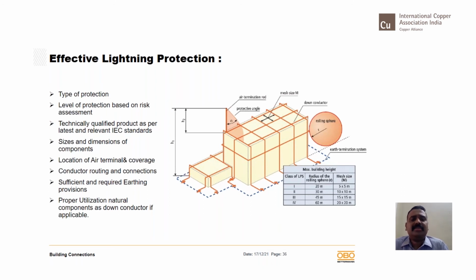Then the location of the air terminal and its coverage. This is very critical, because if you locate a terminal and say a coverage area of this much is being covered in the building, you have completely done the design. Finally, when it goes to the architectural purview, they may say, if you have the terminal here, the aesthetic of the building is getting spoiled, so please relocate it elsewhere. If you do that, obviously that particular area getting protected will be at risk. So safety and aesthetics cannot always go together. I used to tell this as an example.